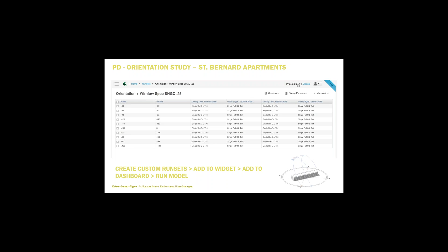0.25 is the code maximum SHGC in Louisiana, zone 2. I knew this would lessen the sensitivity on orientation, so I wanted to communicate that. So we did one run at 0.25 and one at 0.7. We've got name, orientation, and glass specifications. We make the run sets, add them to widgets, add them to the dashboard, and it runs automatically anytime we hit the run simulation button in the Revit environment. This is an example of the output of those two widgets: orientation plus window at 0.7 SHGC, and at 0.25 SHGC.